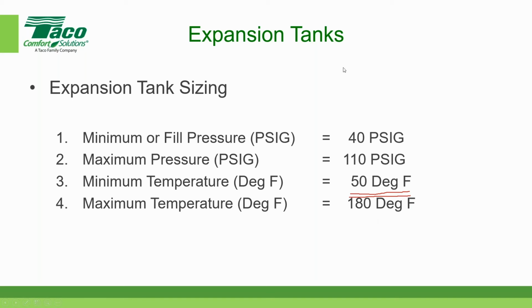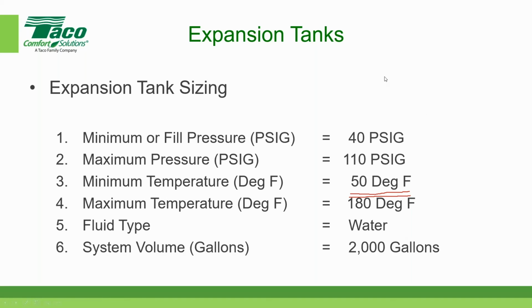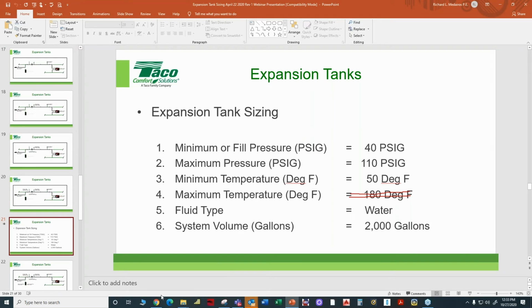We need to know item number 5, the fluid type. And for today's example, I'm using water with a specific gravity of 1.0. And the last thing we need to know is the system volume. And so I've estimated the system volume in my imaginary system to be approximately 2,000 gallons. So now I have all the 6 major categories for sizing an expansion tank. Now I can use that information in my expansion tank sizing app. So I'm going to go live to our website. Click on the website over here.